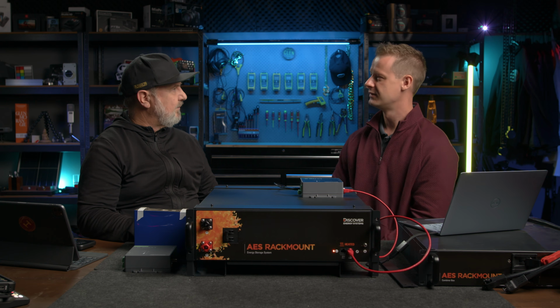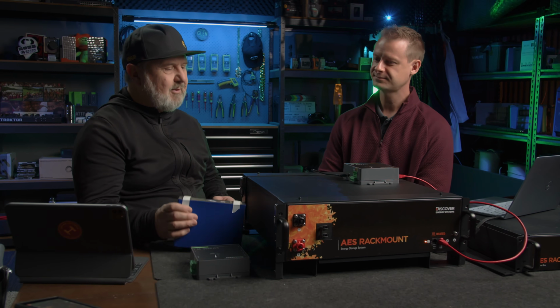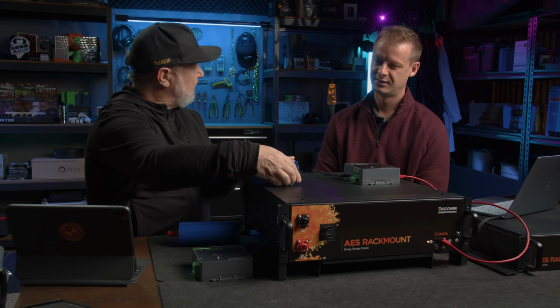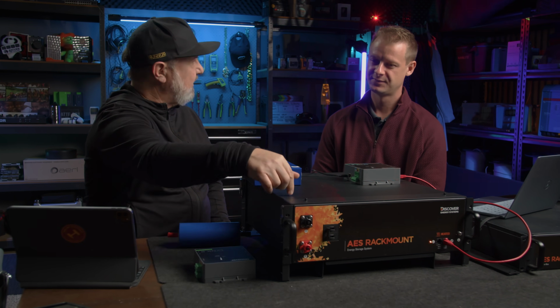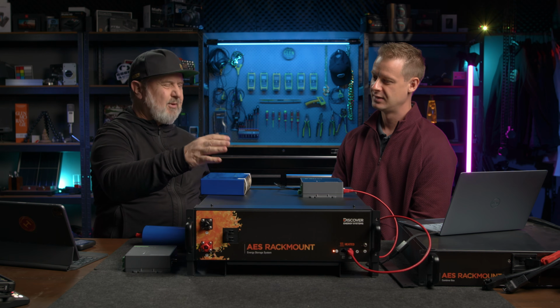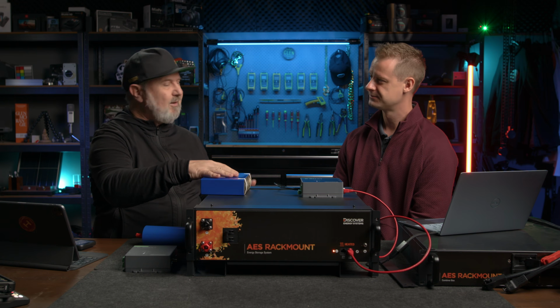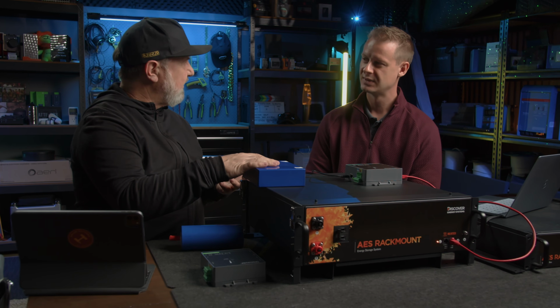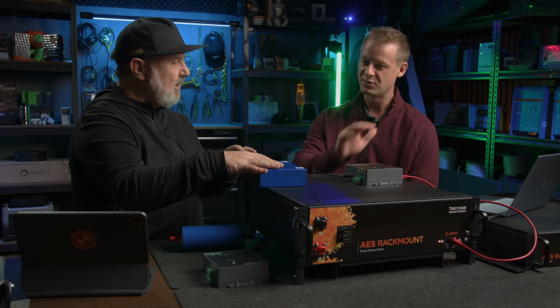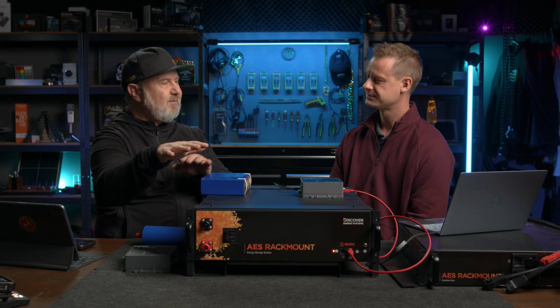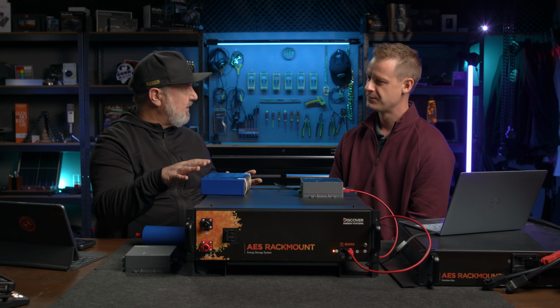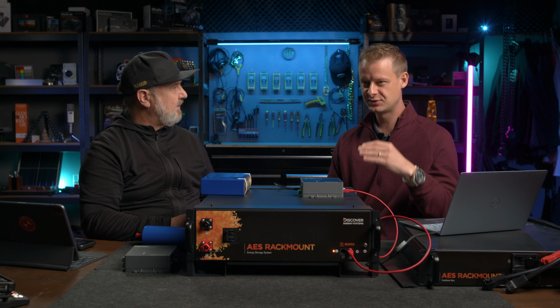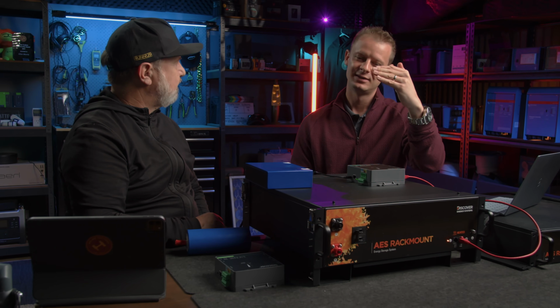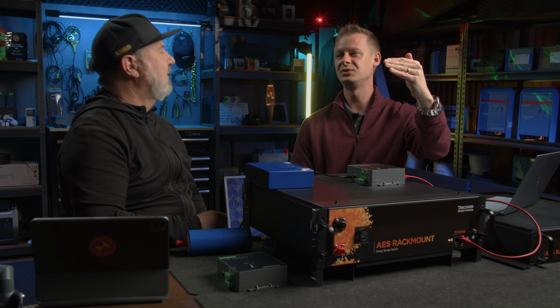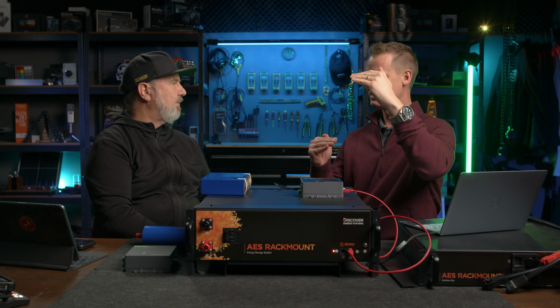To explain it more fully, these cells are connected in series, one to the other, each a nominal 3.2 volt cell, but you start to balance around the 3.35, 3.5 volts per cell mark — though they don't all have to do it at the same time. That's the whole point of balancing. You target the highest voltage and do top balancing, trying to pull down that highest cell and allow the others to catch up.